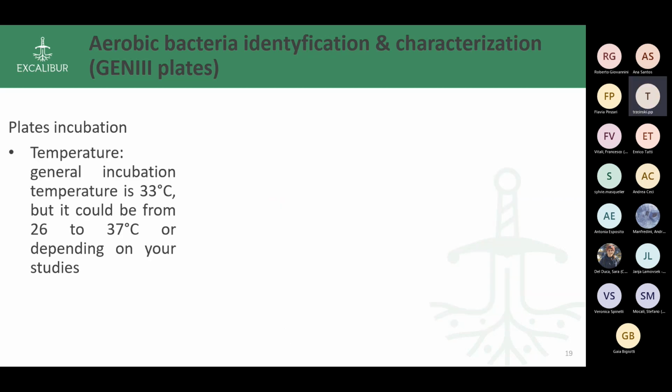So the plate incubation. The default temperature is 33 degrees, but you can change this temperature from 26 to 37. But you can also incubate the plates at other temperatures. Everything depends on your studies. I think that Enrico showed you in his presentation that there are some changes in the bacterial metabolism when the plates were incubated at different temperatures.